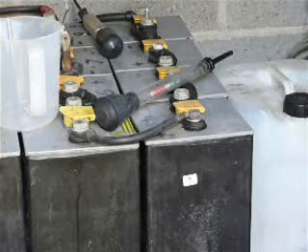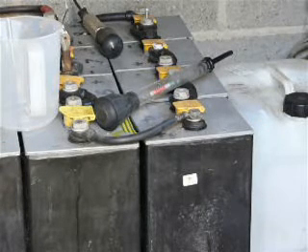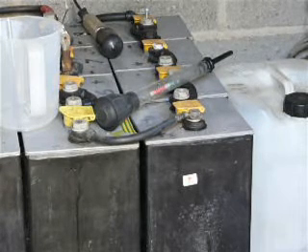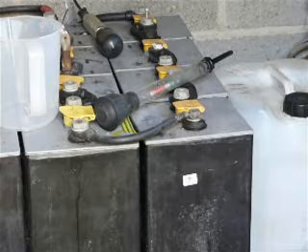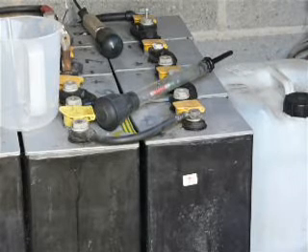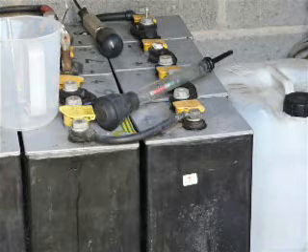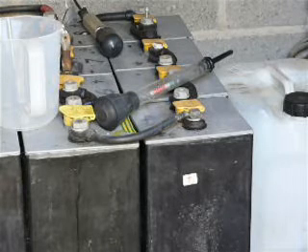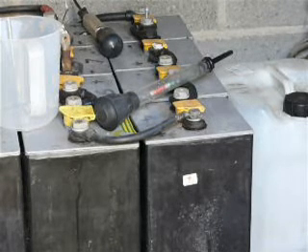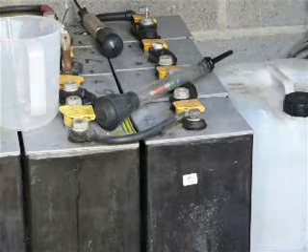As the power in a lead acid battery is used up, the strength of the acid is reduced and lead sulfate is created on the battery plates. This lead sulfate can cause damage to the battery plates if the battery is left discharged for any length of time.